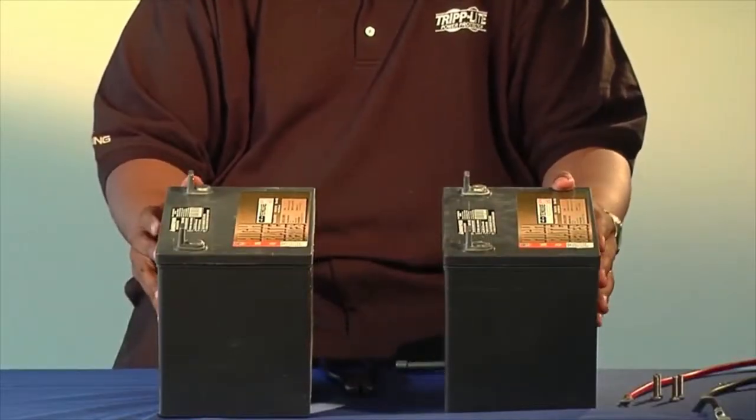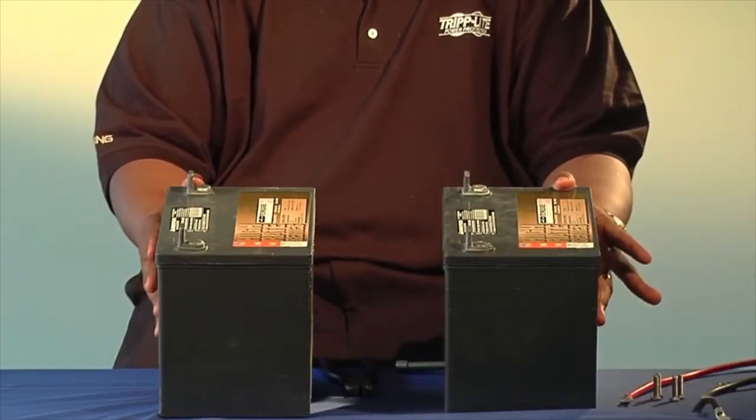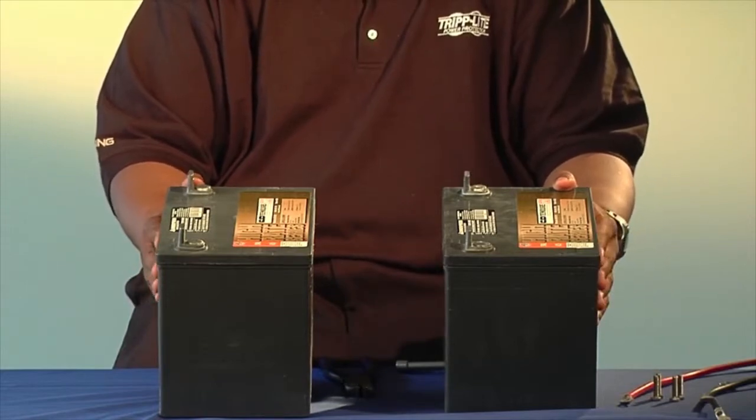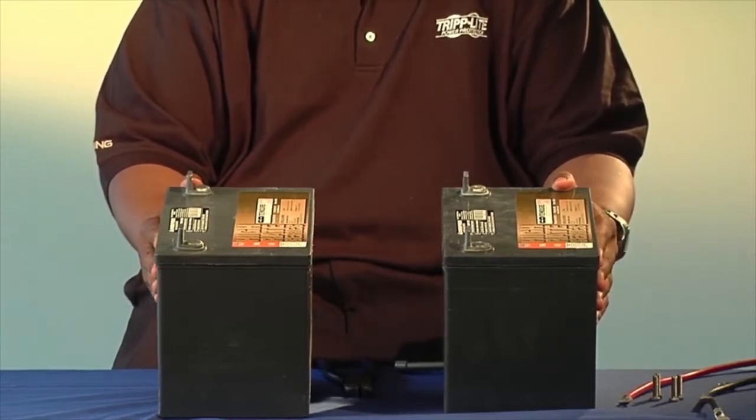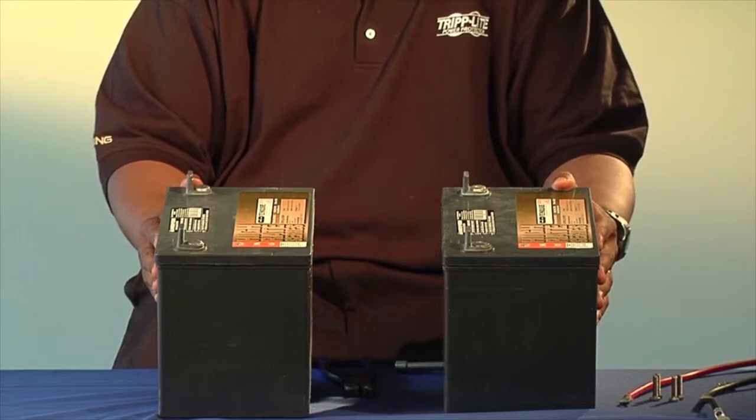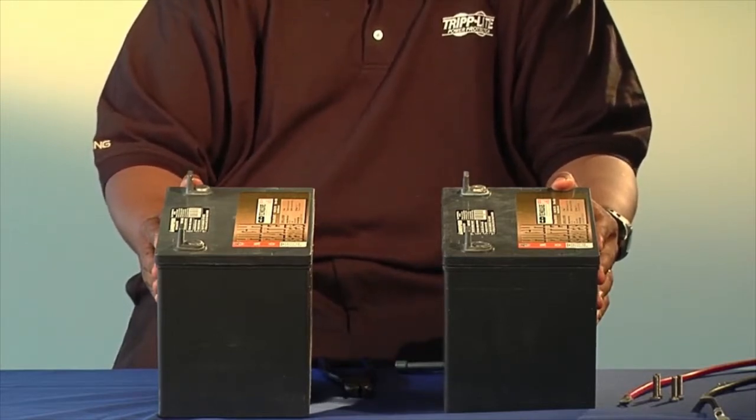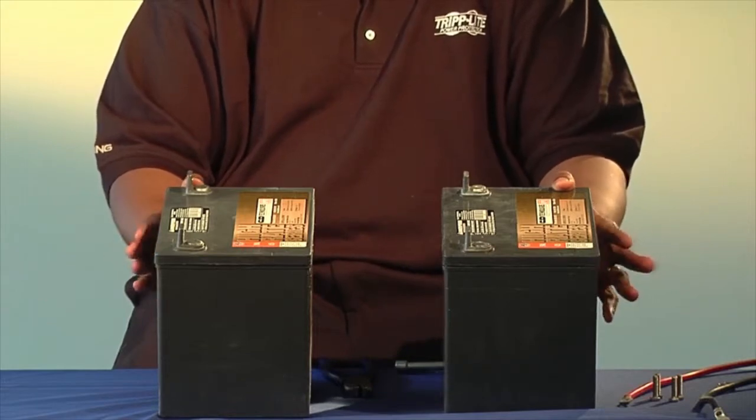Parallel connections increase the ampere hours of two batteries. For example, if we had two 6-volt batteries at 6 amp hours, once we put the two batteries in parallel, they would become one 6-volt battery at 12 amp hours. Let's begin.